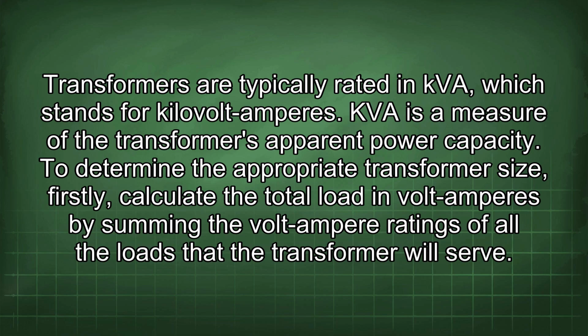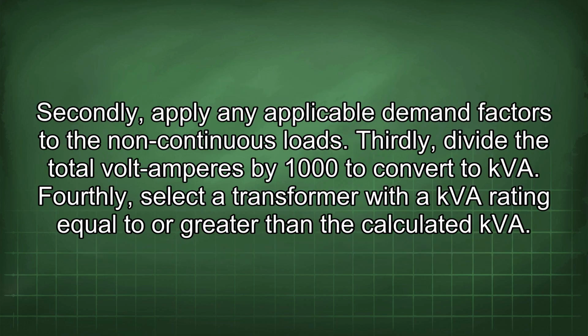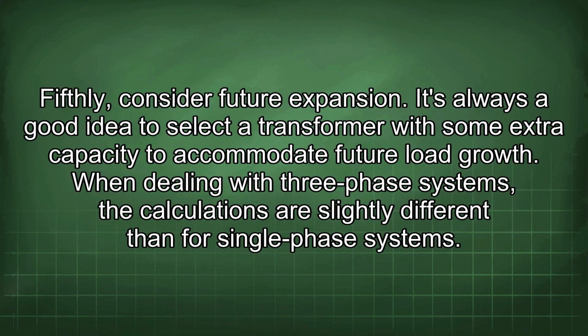To determine the appropriate transformer size, firstly calculate the total load in volt amperes by summing the volt ampere ratings of all the loads that the transformer will serve. Secondly, apply any applicable demand factors to the non-continuous loads. Thirdly, divide the total volt amperes by 1000 to convert to kVA. Fourthly, select a transformer with a kVA rating equal to or greater than the calculated kVA. Fifthly, consider future expansion.